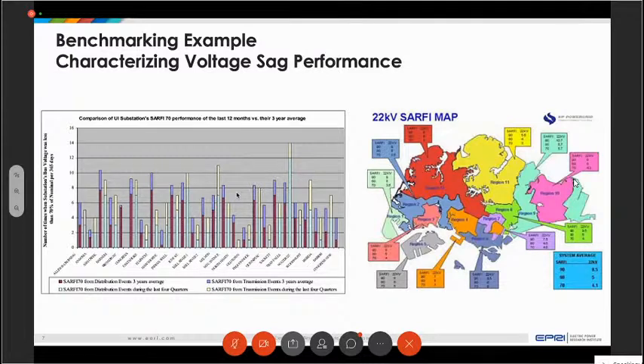Then I also included what Power Grid in Singapore Power calls their SARFI map, and they have probably one of the best performances in the world. The system in Singapore is 100% underground, with a very low number of faults and almost no interruptions, but they still have some faults. And so their SARFI 70 is about 4.1 events per year over the whole system.